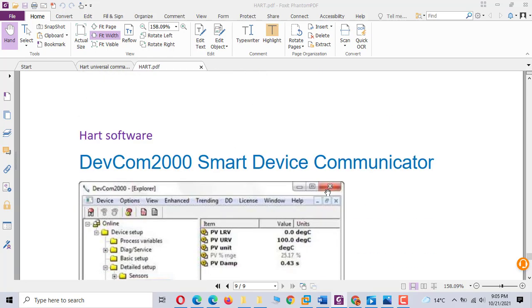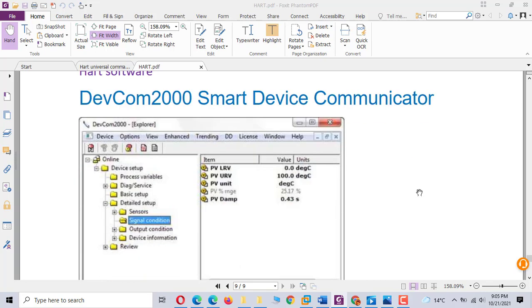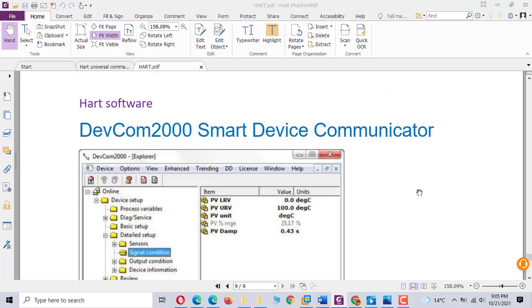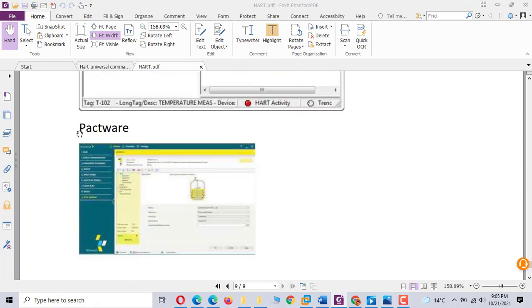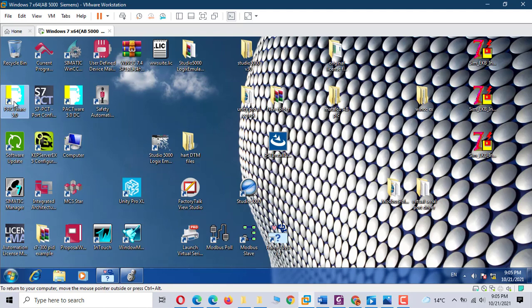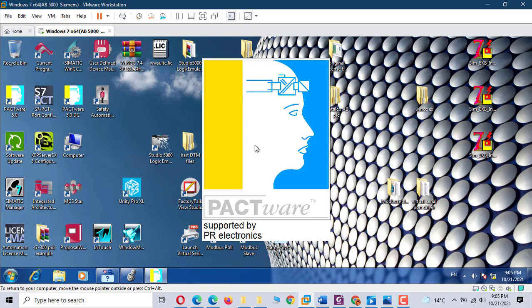Okay, it's Hart. We can use software for configuration of everything. The first one is the DevCom2000 Smart Device Communicator, but this is more expensive, so we don't use this one. But there is PACTware, which is free software. We can use this one, PACTware 5. If your connection is to a Hart transmitter, we can do the configuration this way.